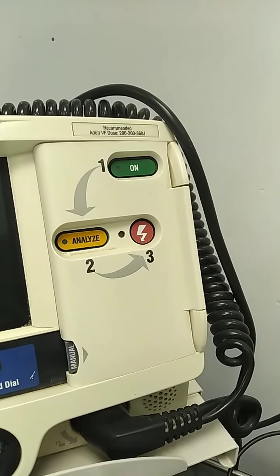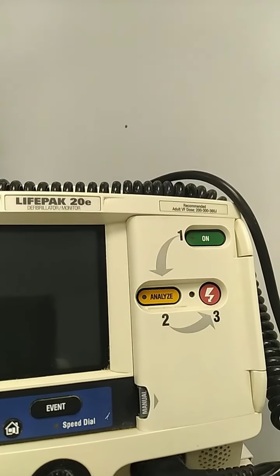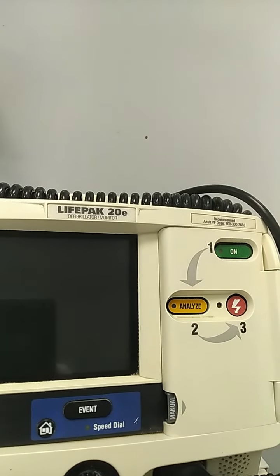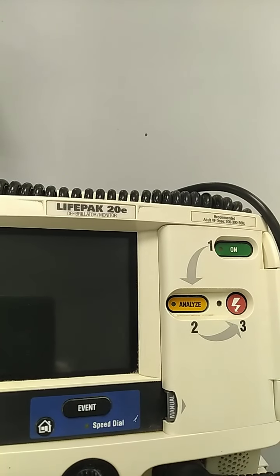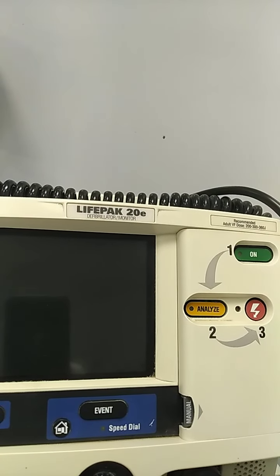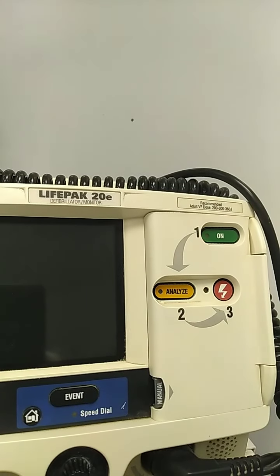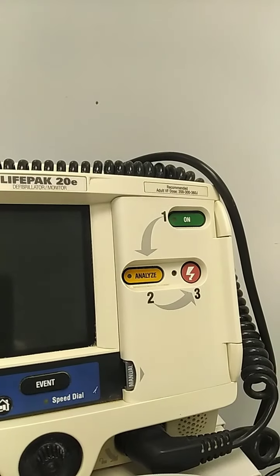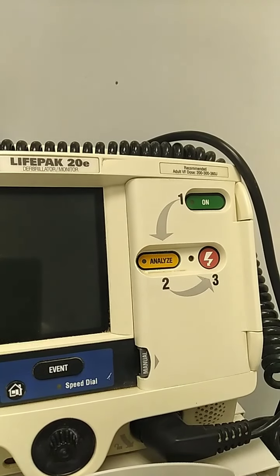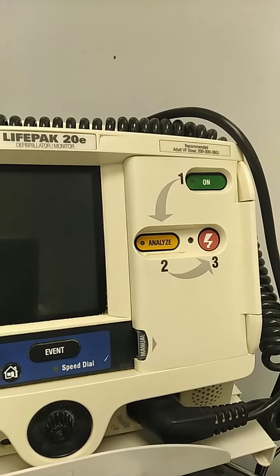Okay, let's talk about this LifePak machine, and I will show you how it works. The LifePak device is able to defibrillate, cardiovert, pace, and more in an emergency. It is important that you are able to confidently connect and run this device for your decompensating patient. The machine is tested every day, once plugged in and once unplugged. If you're running a user test, leave the machine plugged in, and after a successful user test, document it in the binder.